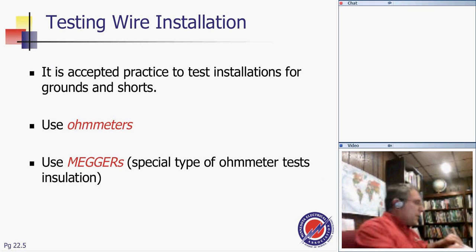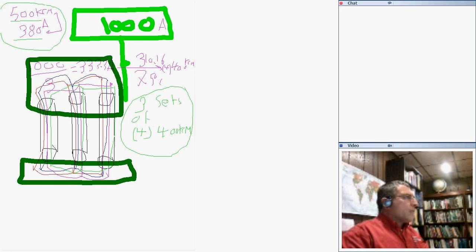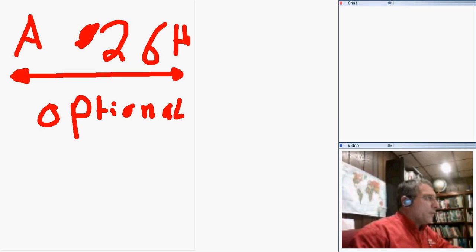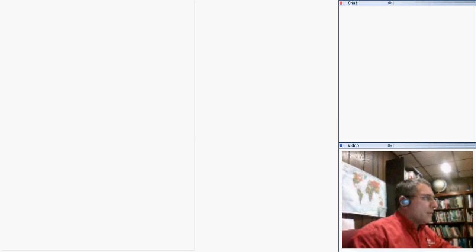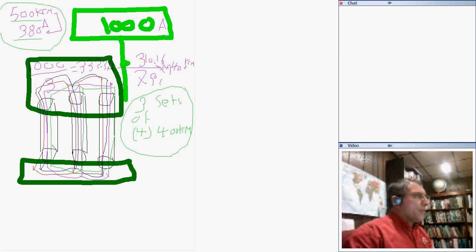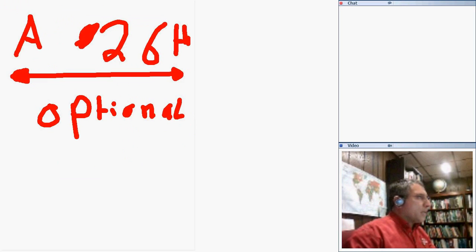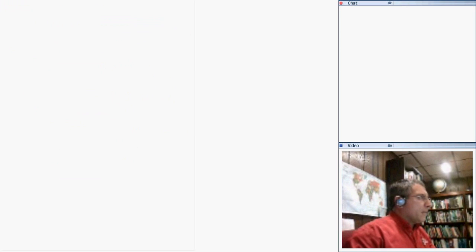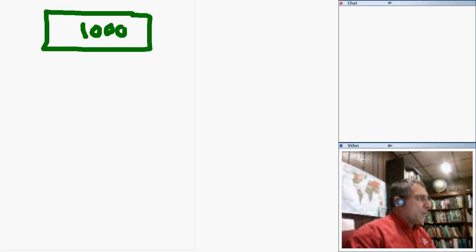One thing is I have to show you a few things in the NEC code book. Oh, let me go, I must have moved fast. The question is, what is the rule of thumb for sizing the neutral? Here's how I size the neutral. Let's just size the neutral for this system that we've just done. I'm going to size the neutral for the switch gear here, and that shouldn't take much work, guys. Let me just go grab this. So the neutral, I have my 1000 amp, and I'm going to do my neutral.